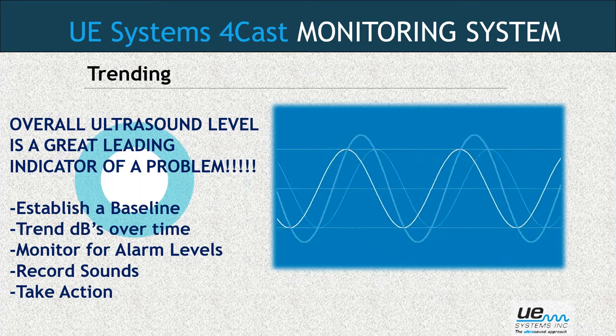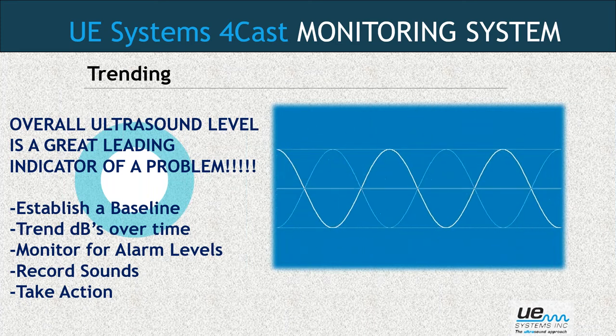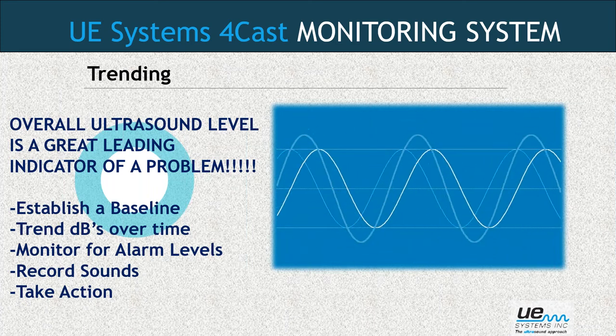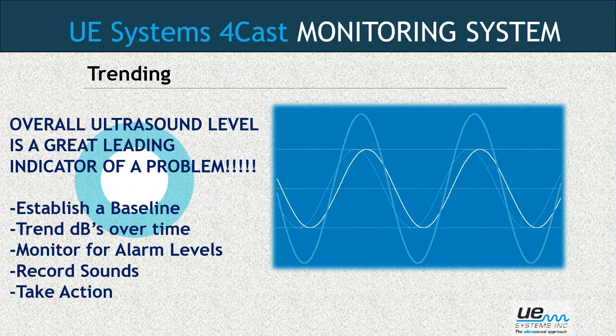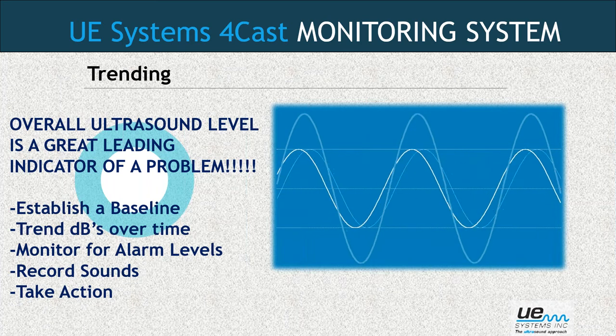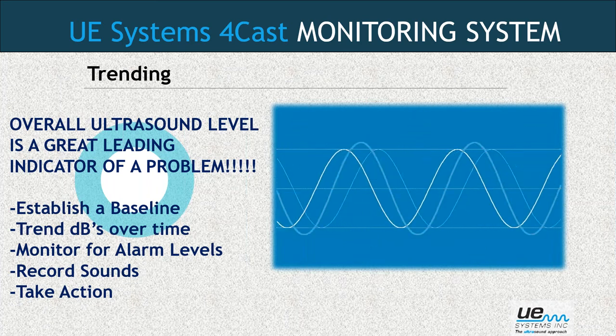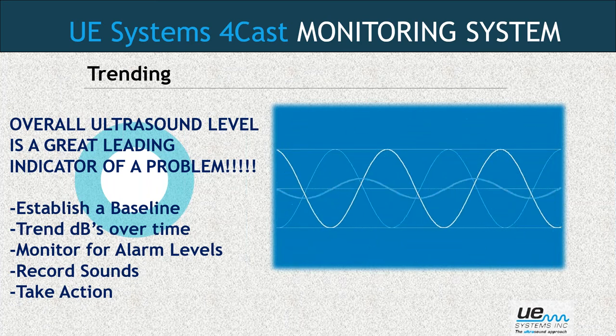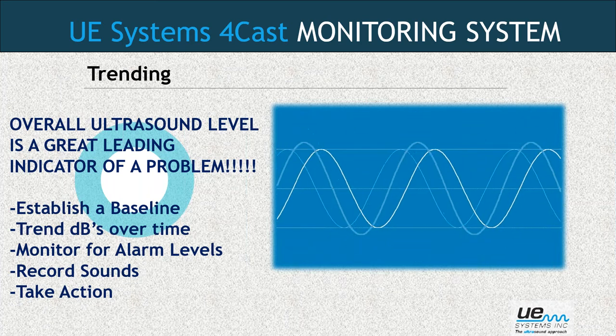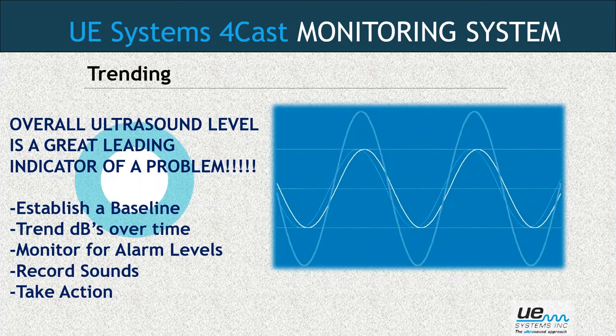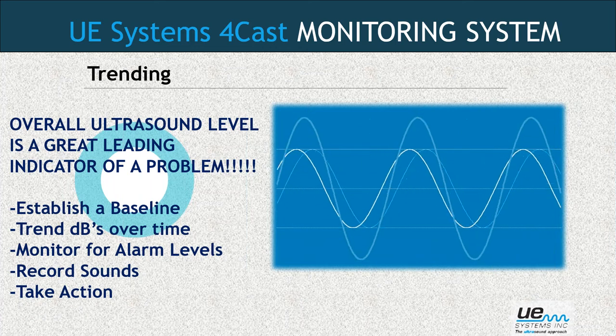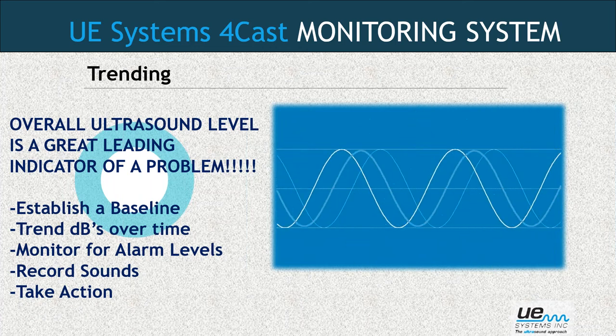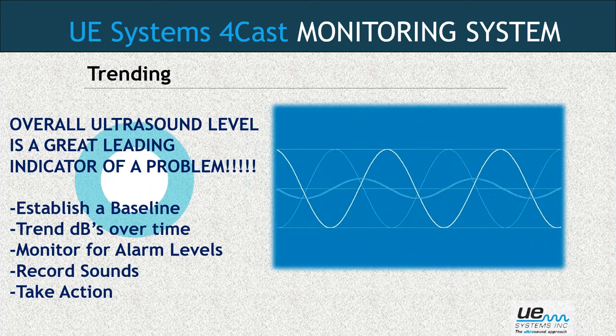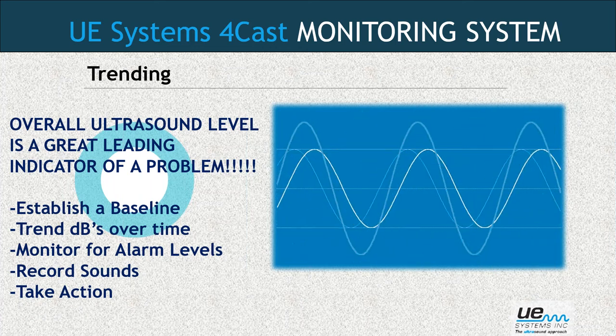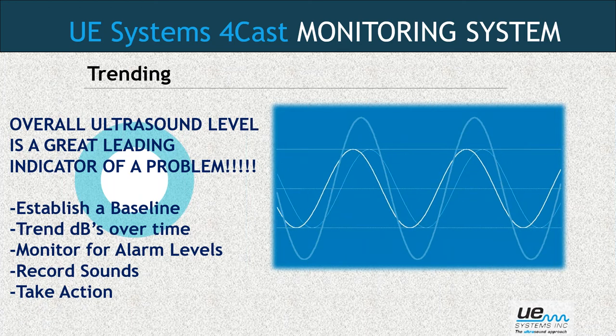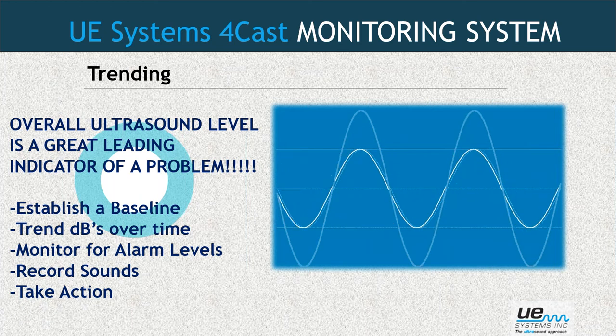So by using a dB number and assigning an alarm level, we can basically take the increase, wait till it hits an alarm, and then we can record sounds and we can take action. So trending is really a great application for ultrasound on rotating equipment, and that overall ultrasound level is going to be a very early warning that something's changed and that we need to do something different.